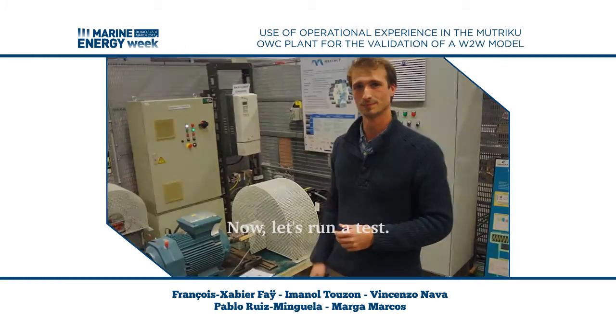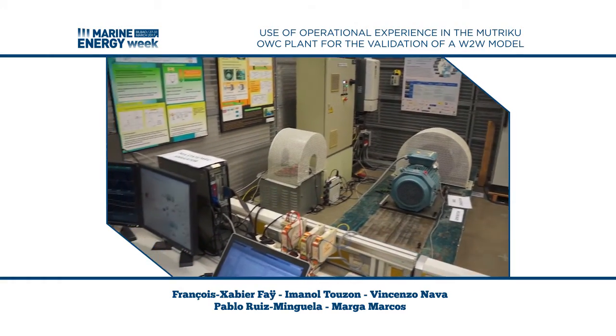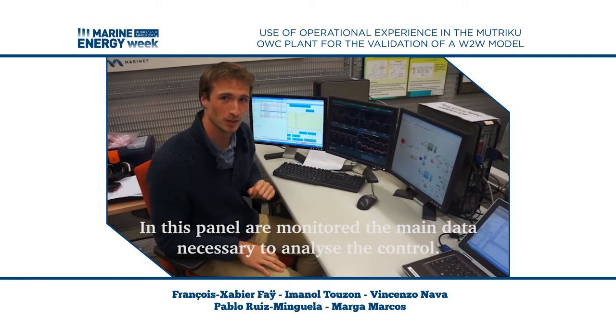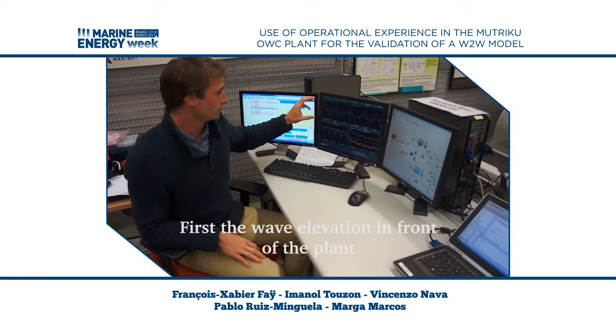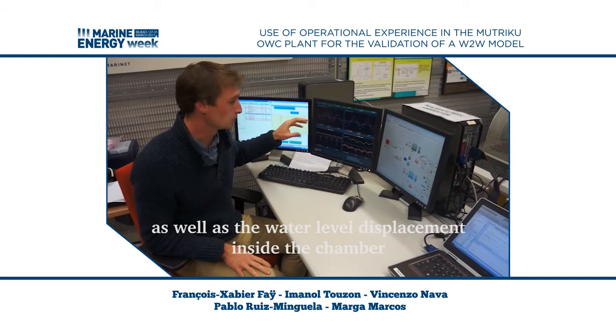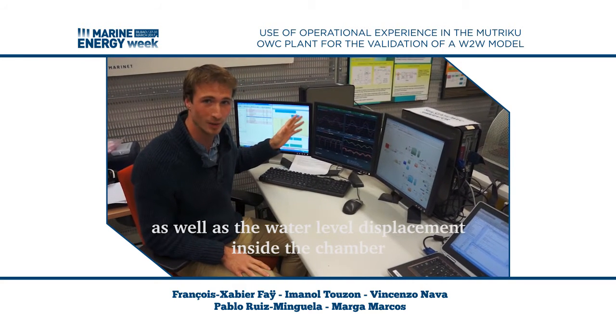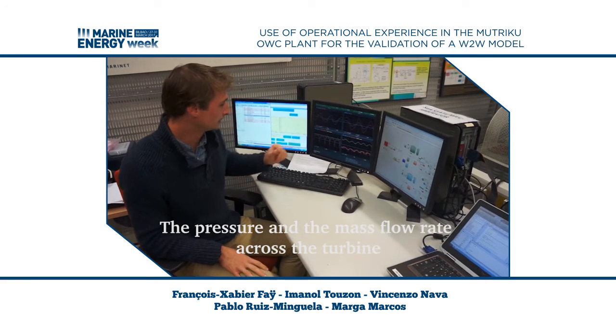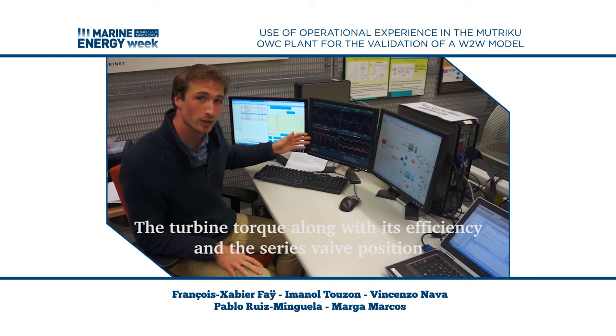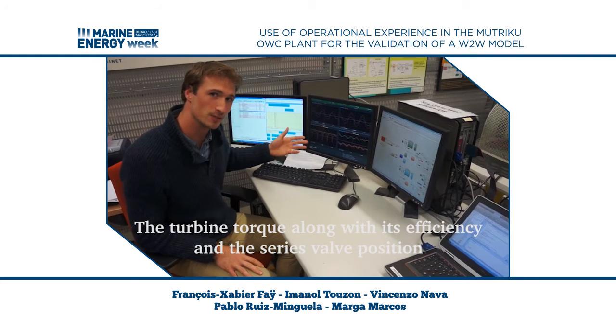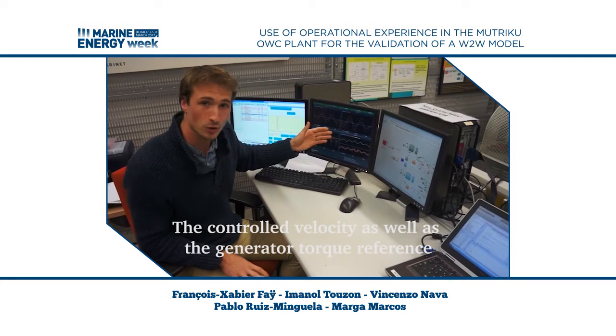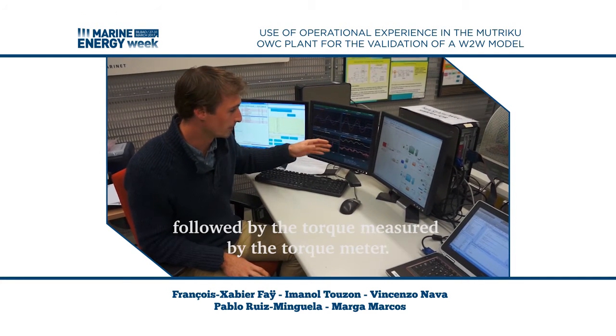Now let's run a test. In this panel, I monitor the main data necessary to analyze the control: first, the wave elevation in front of the plant, as well as the water levels inside the chamber, the pressure and the mass flow rate across the turbine, the turbine torque along with its efficiency and the series valve position, the control velocity, the generator torque reference, and the torque measured by the torque meter.